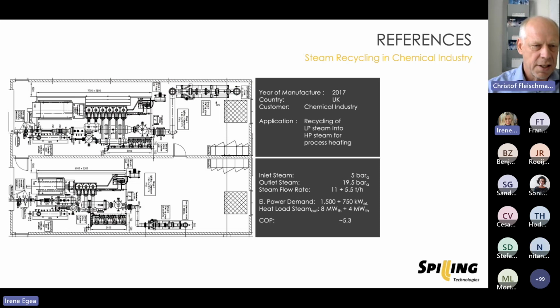Here is another installation at a chemical plant in the United Kingdom, where steam is recycled from cooling of an exothermic reaction, available there at 5 bar absolute level. And this steam cannot be used at this plant at this quite low pressure level, but they have a demand, or a steam distributing pipe again, at about 20 bar absolute. And so the steam is compressed onto this pressure level. Here we have a compression ratio of about 4. And by this we reach a COP factor of about 5.3.